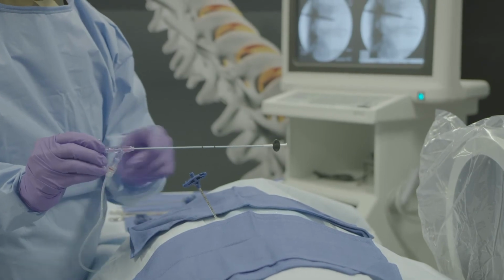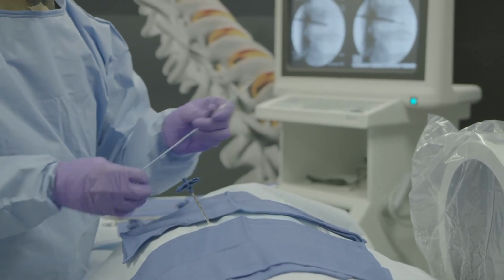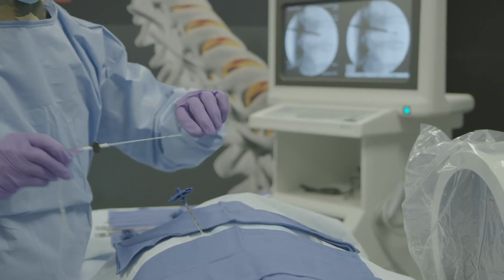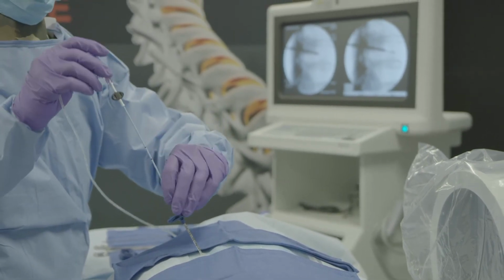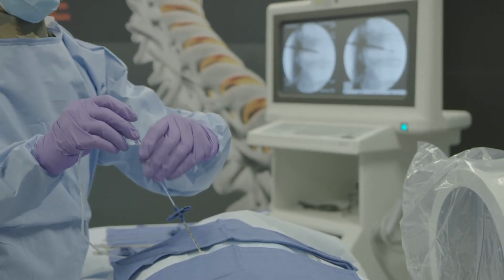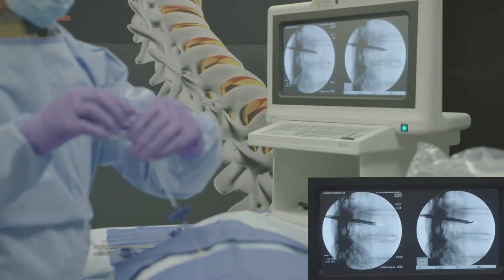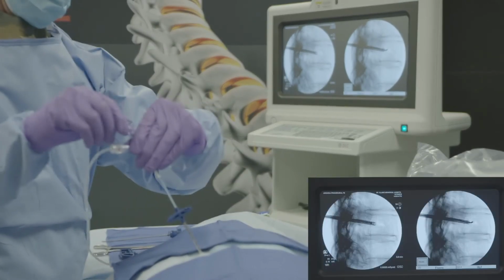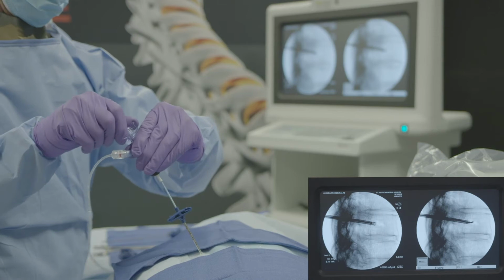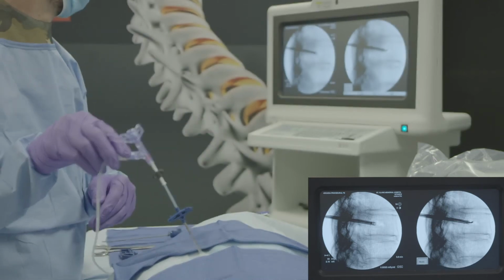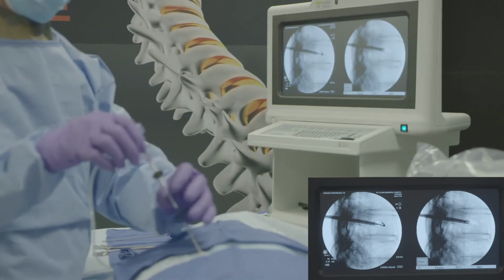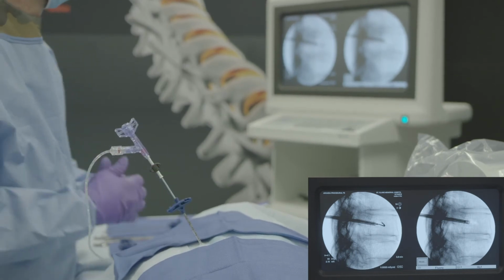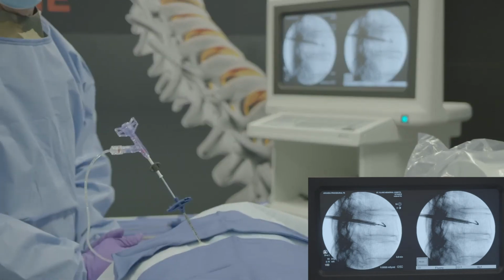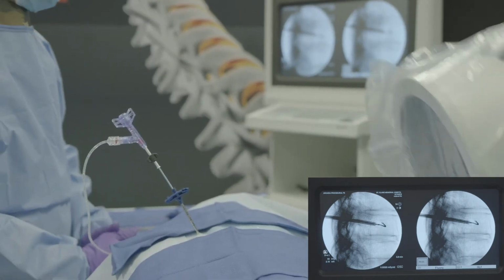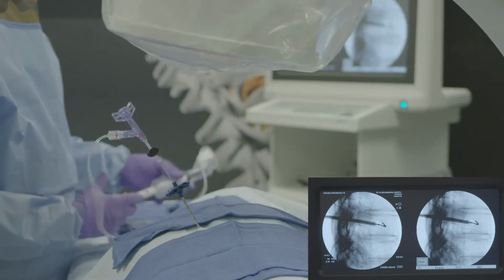The Arcadia balloon is equipped with a resheathing tool that can be locked into the hub. Do not remove. In the lateral view, insert the Arcadia steerable balloon into the access cannula until flush with the distal tip. Begin turning the steering handle on the Arcadia steerable balloon catheter clockwise to aid in directing the distal portion of the device when the distal radiopaque marker of the balloon has exited the working cannula.